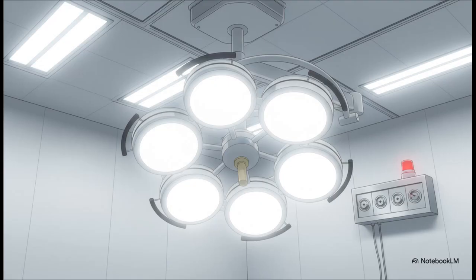And you obviously can't afford to lose power in the middle of a procedure. The utilities in this room are built on extreme redundancy. The main operating fixture gives off shadow-free lighting with minimal heat. Crucially, the ceiling lights and the operating lights are wired on entirely different circuits, so if a fuse blows, the surgeon isn't suddenly left in the dark. There are also continuously tested storage battery lights for power failures, emergency signal lights that the anesthetist can easily grab, and flush-mounted connections for specialized equipment like heart-lung machines.